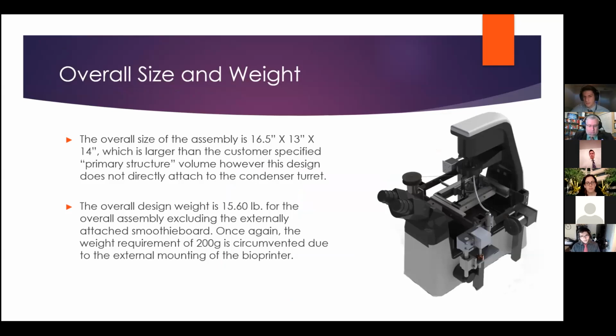We calculated around an hour for assembly, but one of the benefits is that once it's assembled, no further assembly is required except for replacing the syringe and needle. The overall assembly is only 15 pounds. It was meant to be built once and be ready for use at any moment. And because the overall head, the upper head of the microscope, can pull off or be pushed back, it can easily go over the microscope.